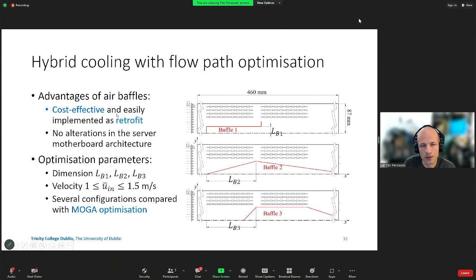But again, the benefit of this approach is that with the baffles, even though they're quite simple, they're cost effective, obviously, to implement, and we can do this in a retrofit scenario. So we could actually go to one of our industry partners and say, look, here's an existing system. We can take out the heat sinks from the CPUs, replace them with liquid-cooled cold plates, and introduce a few baffles that could be 3D printed or made in some other way to improve the waste heat recovery potential of this particular rack, for instance.